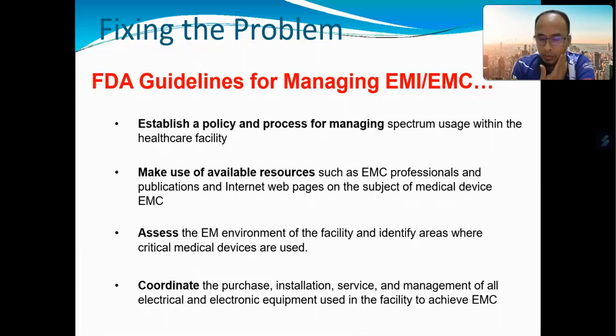And basically, we also think about poor integration of medical devices. Poor integration can cause EMC issues, even if each device individually meets standards. So sometimes when we put a few medical devices in one place, we have to make sure that they have electromagnetic compatibility between each other, so that one medical device will not interrupt other medical devices in the same area, right?